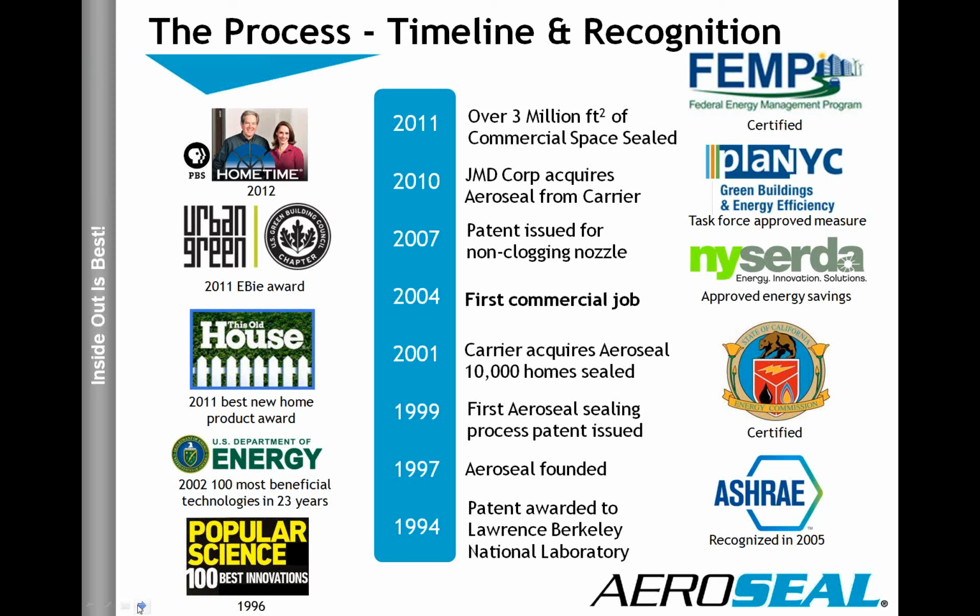Appreciate that overview. And yes, that was an absolutely phenomenal project and very successful. And that was at a 40% leakage rate on a total fan flow. And as we all know, and we'll show here in just a second, and what we stated earlier, duct leakage is not a matter of do the ducts leak. It's always a matter of how much, right?